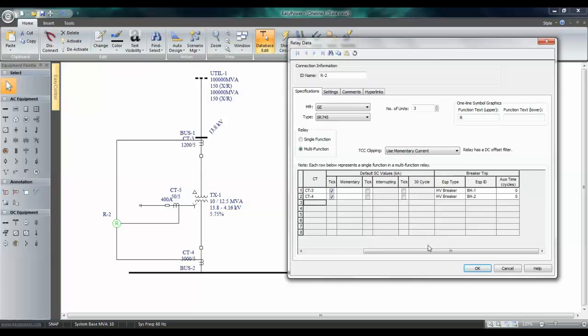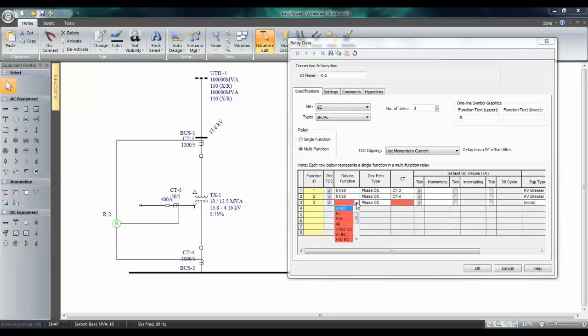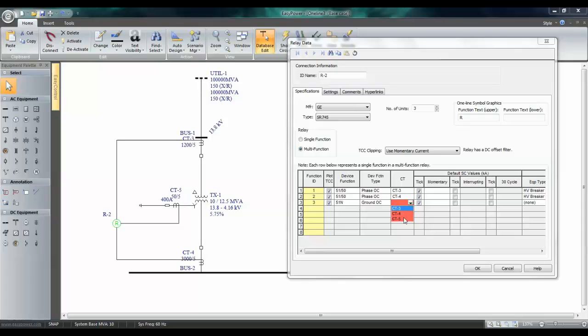Next, we will enter the third device function, which is the ground trip for faults on the secondary side. So, this is device function number three. And I'm going to choose 51N, and fed by CT number five.